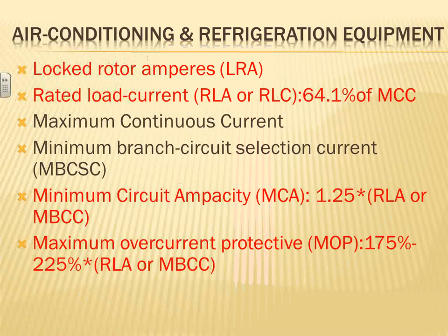When you were circling stuff, I think there was an opportunity for confusion. Locked rotor amps: when he said you multiply something by six, you circled LRA at the end. If they don't give you locked rotor amps, you can estimate it by multiplying the rated load amps by six. Absolutely, if it's not given. Oh, I'm sorry, I meant locked rotor amps, if it's given. My apology.